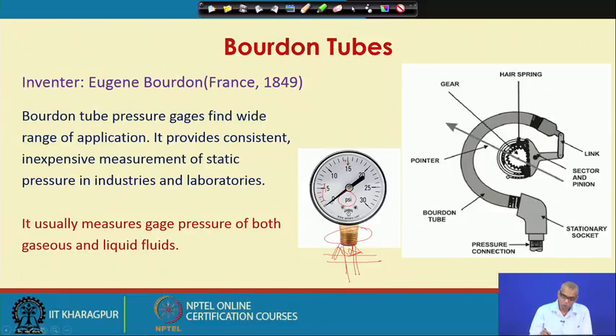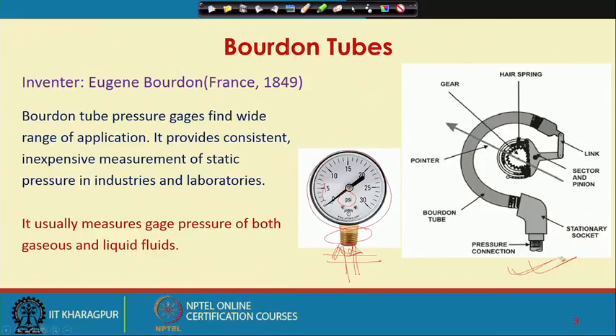Now, if you open this and look at the inside, you will see this. You may also see something called a diaphragm element, which we will talk about later, but in the Bourdon tube based pressure gauge, you will see this. There are pressure gauges which look exactly similar to these from outside, but when you open them, instead of a Bourdon tube there can be a diaphragm element, but we will talk about that later. So, today we are talking about Bourdon tube pressure gauges. If you open this, what you will see is this. This is known as a Bourdon tube.